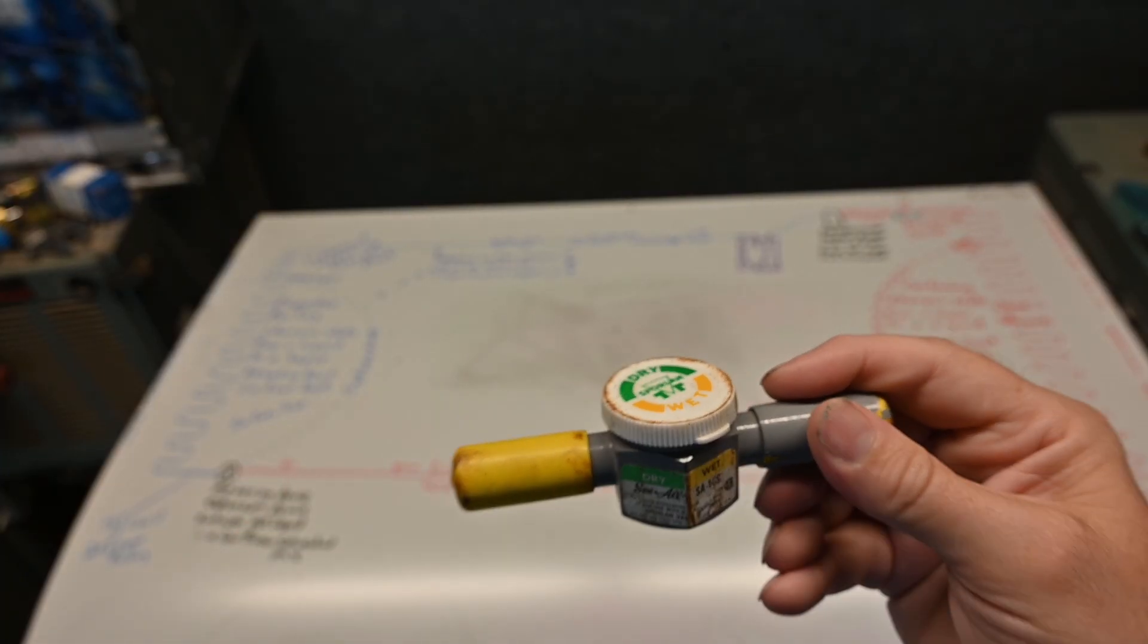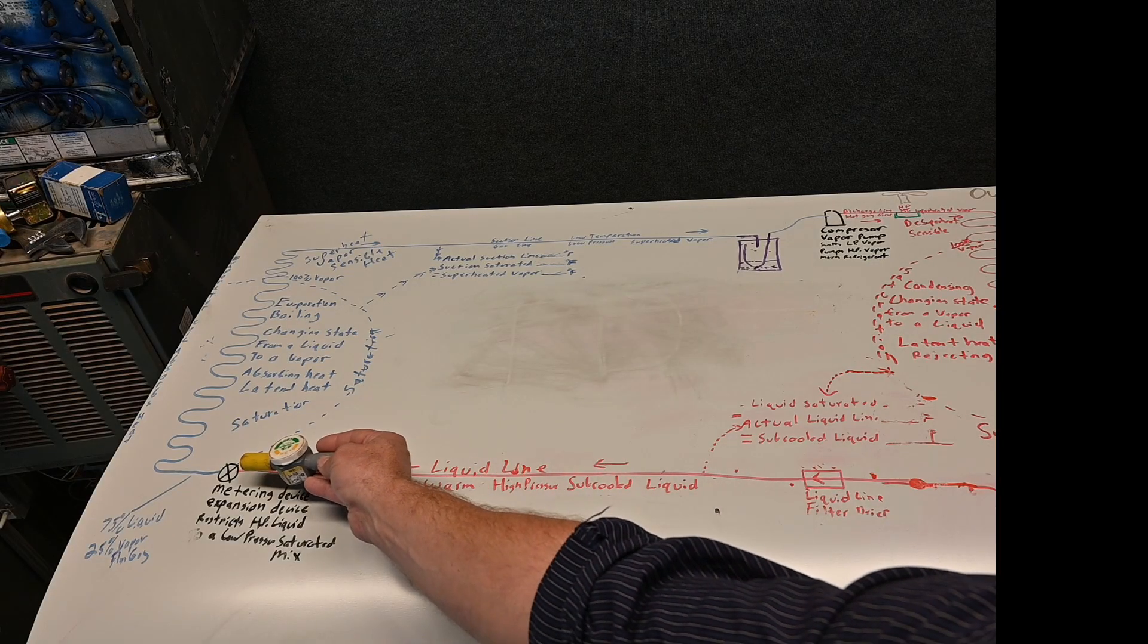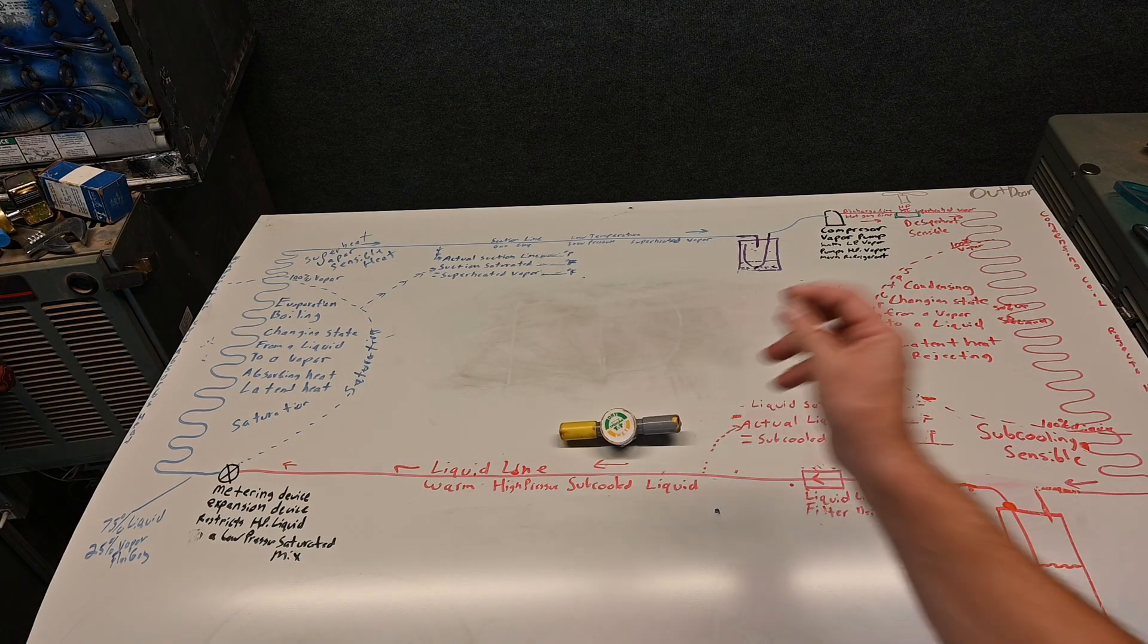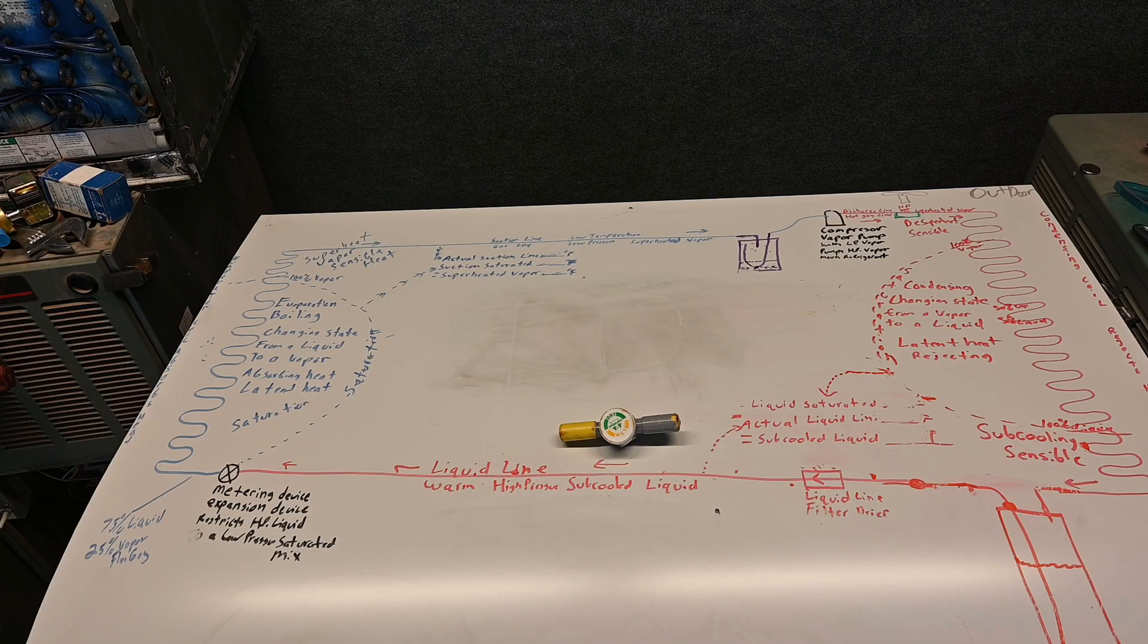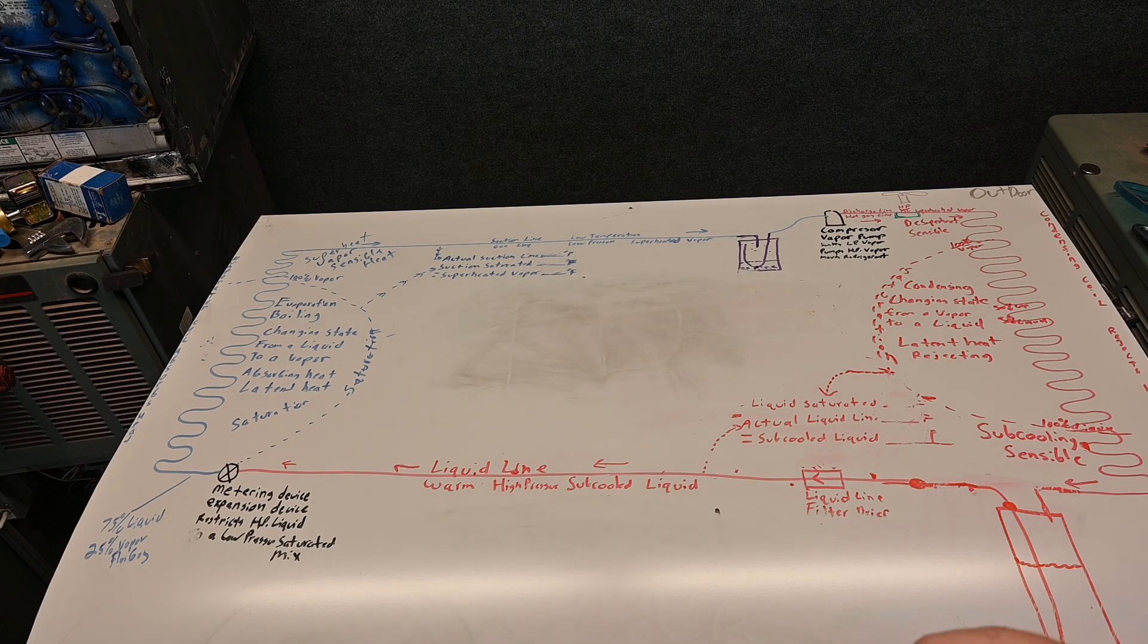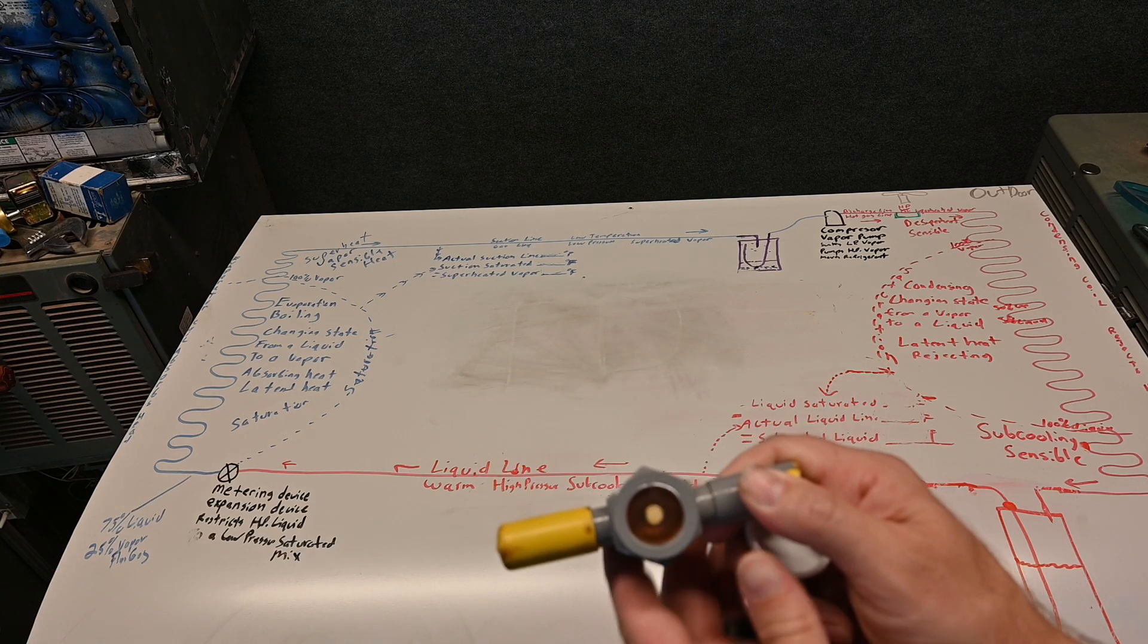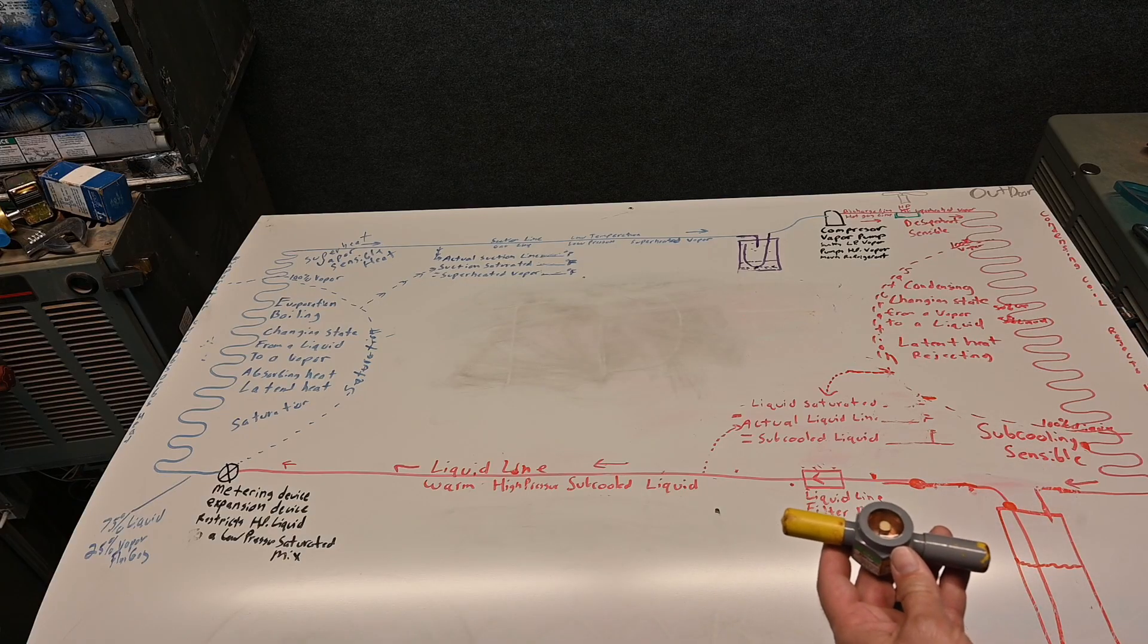So this sight glass on a refrigeration cycle anywhere in the liquid line even up to our metering device. The sight glass can be very useful for refrigeration, but for residential air conditioning it's not as much. The reason is, even though you have a solid column of liquid right here doesn't mean that you would have enough subcooling in the unit for the manufacturer specifications.